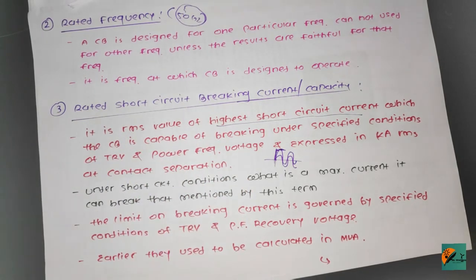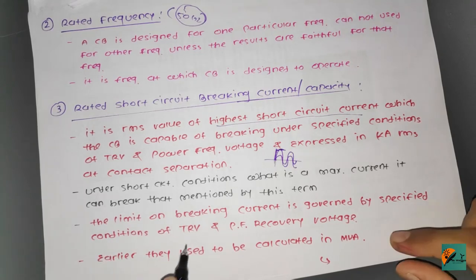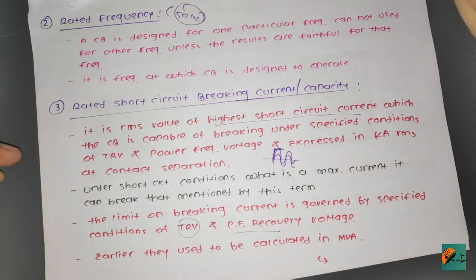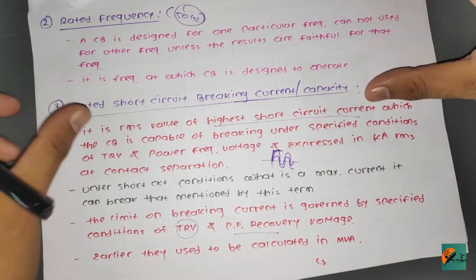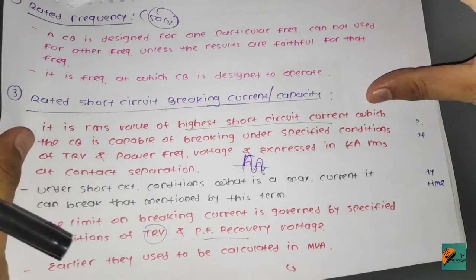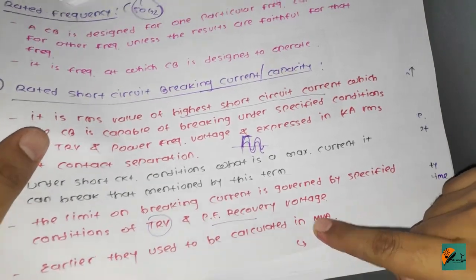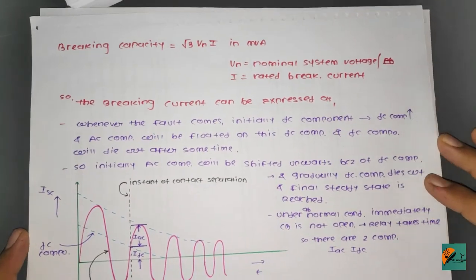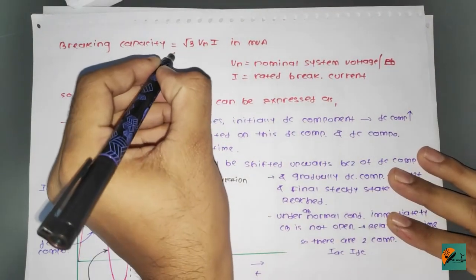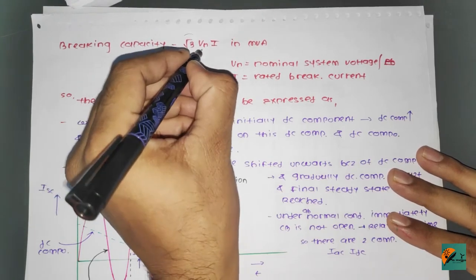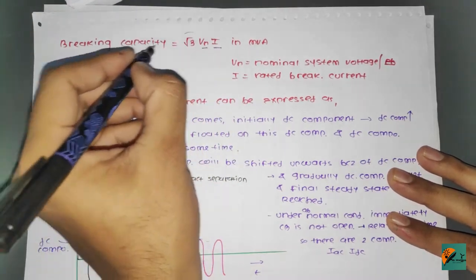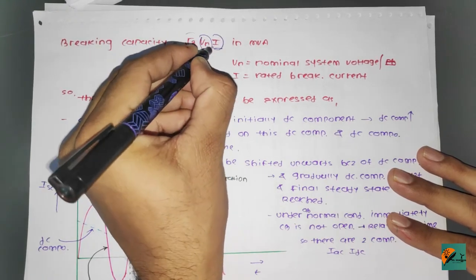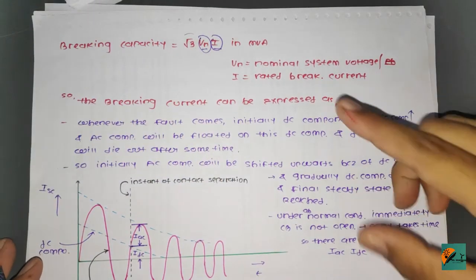The limit on breaking current is governed by specified conditions such as transient recovery voltage and power factor recovery voltage. In earlier days, breaking capacity was expressed in MVA so that fault levels could also be determined. Nowadays, breaking capacity is expressed as: root 3 × nominal system voltage × rated breaking current, in MVA.